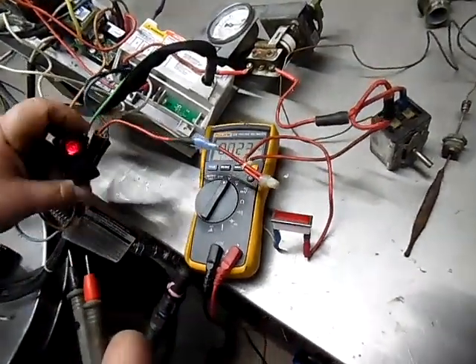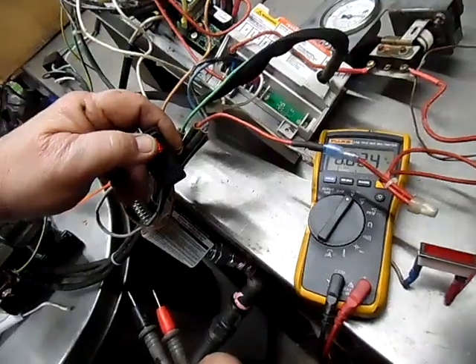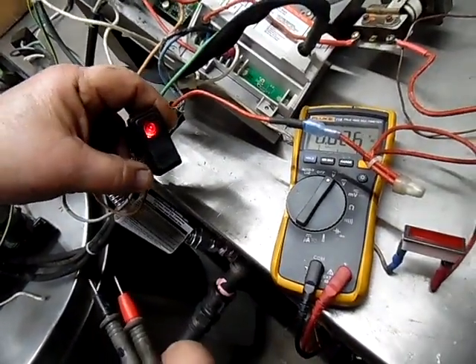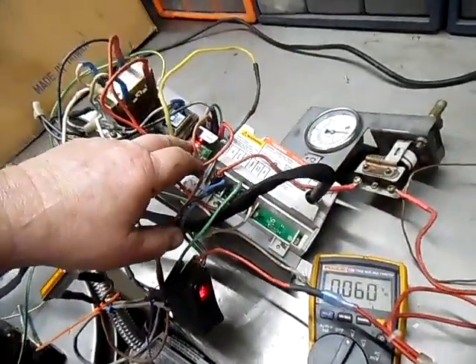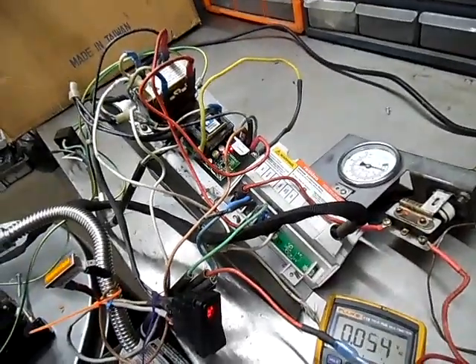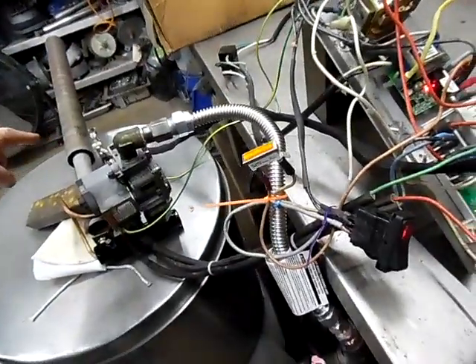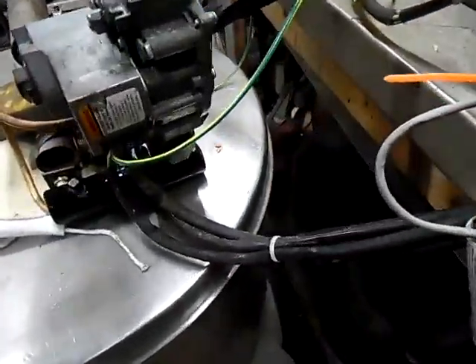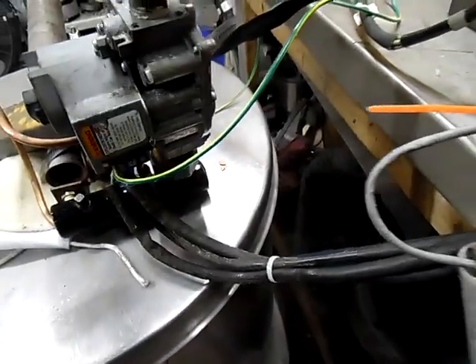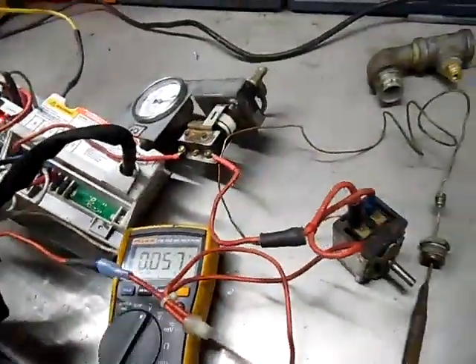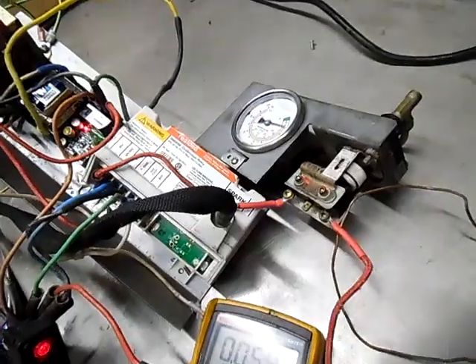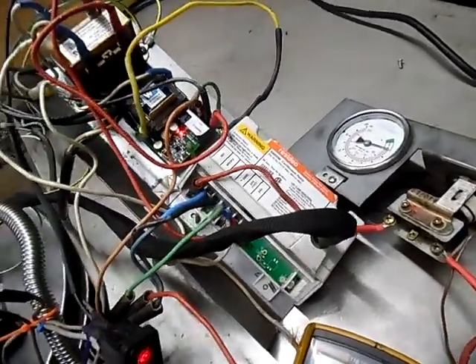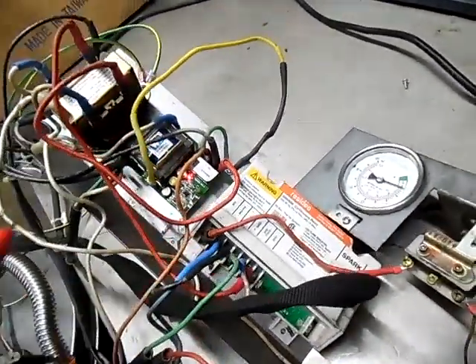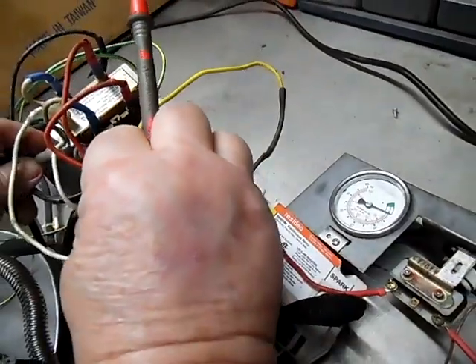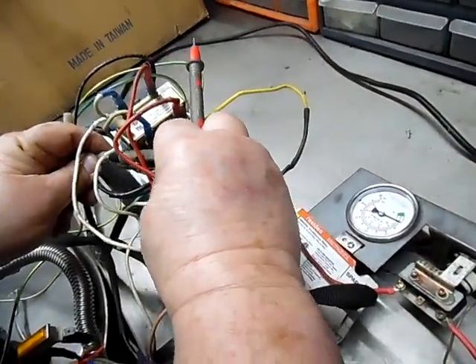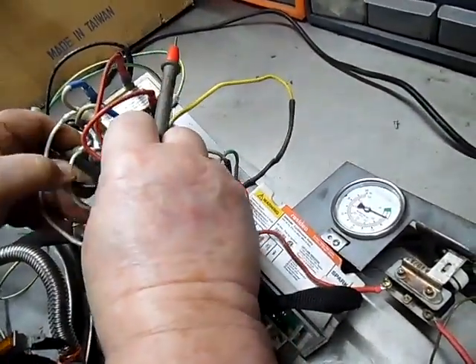In this particular case, you notice I flipped the switch on. You see the red light came on the water board, meaning it's satisfied. And if you listen, you'll hear the spark. Right now I don't have gas on, and this is a continuous box, so this box will continue to spark, trying to light it. Okay? And if you notice here, I'm going to go into my common wire, which is the white, which ties into everything.